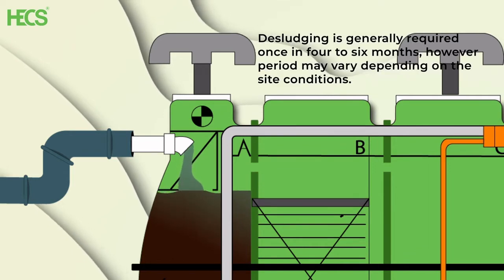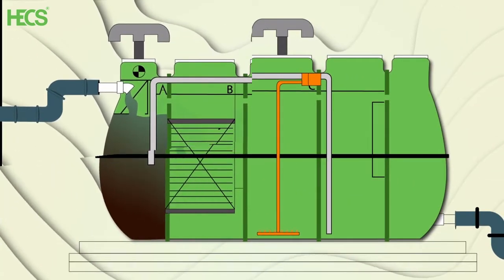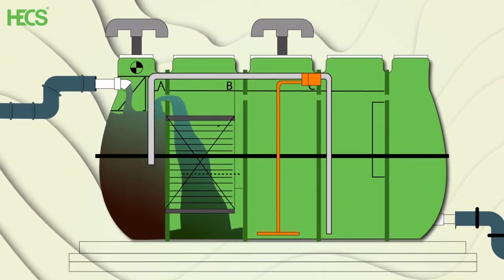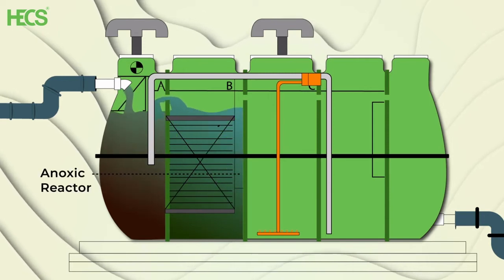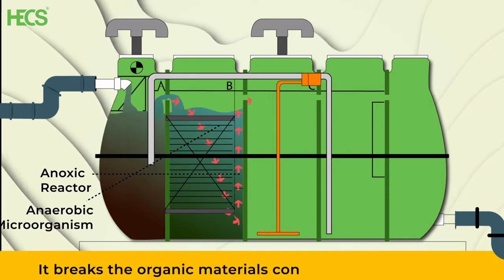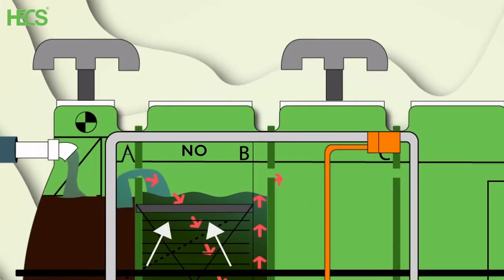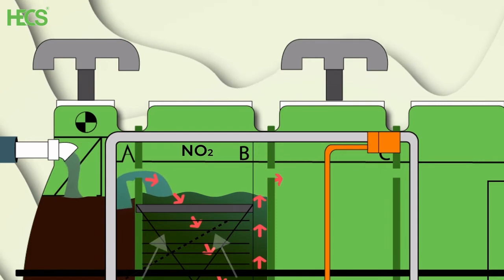However, the period may vary depending on the site conditions. The sewage then overflows from the sedimentation and equalization chamber into the anoxic reactor. This chamber consists of anaerobic microorganisms, which break the organic material contained in the sewage. Denitrification process also takes place in this chamber.